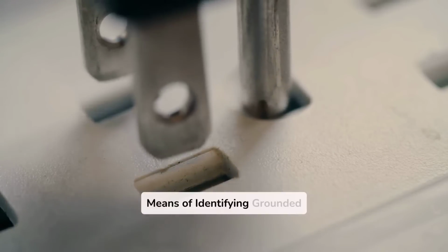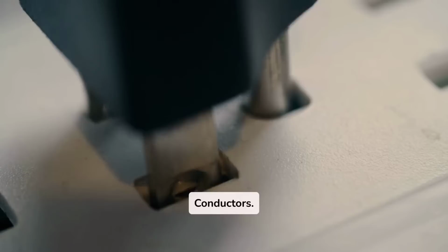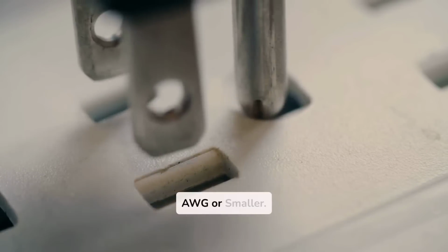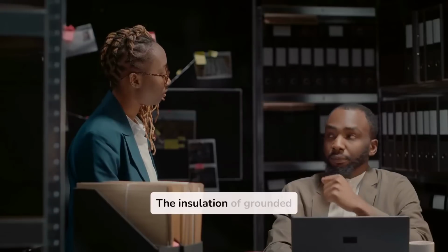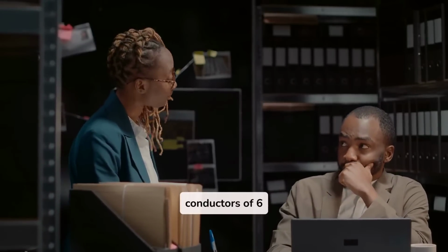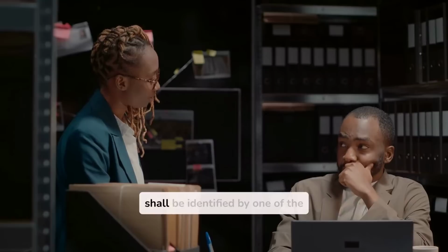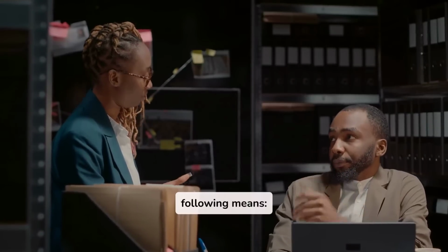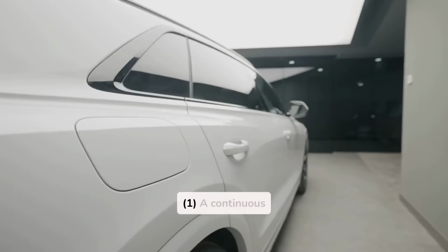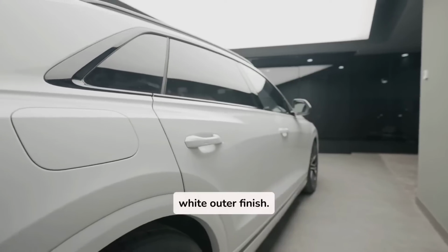200.6 Means of identifying grounded conductors. A. Sizes 6 AWG or smaller. The insulation of grounded conductors of 6 AWG or smaller shall be identified by one of the following means. 1. A continuous white outer finish.